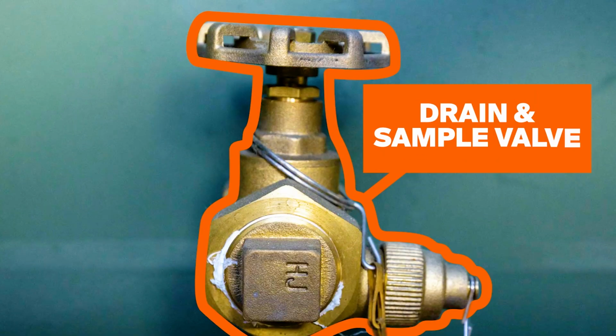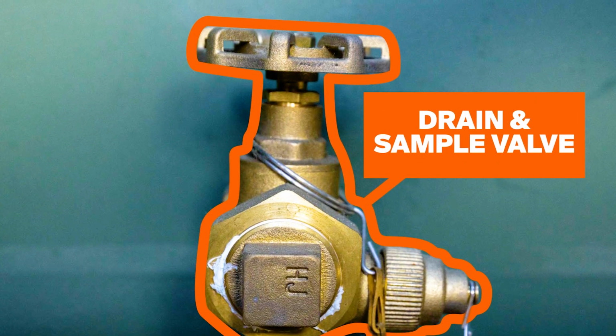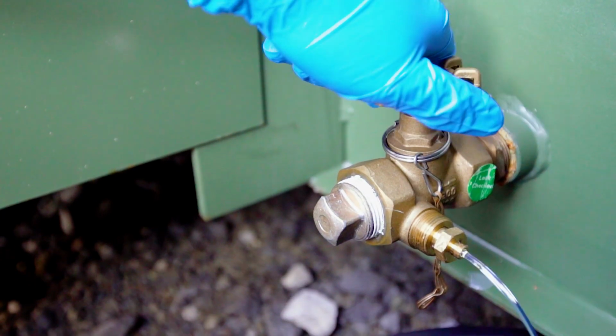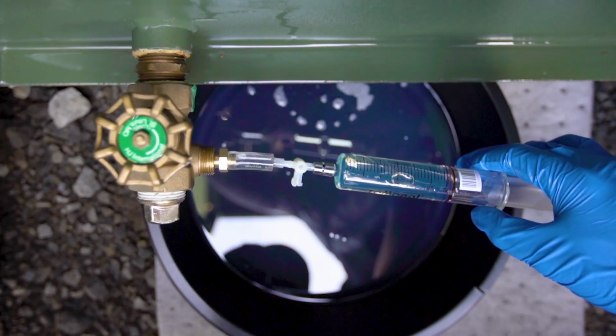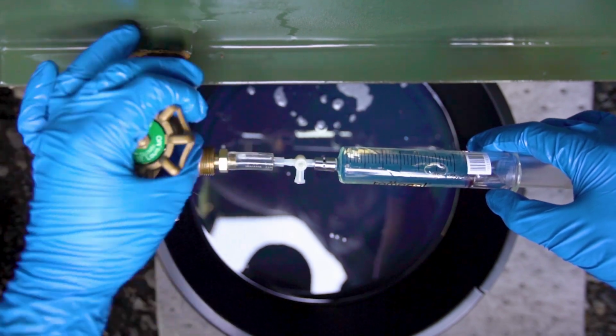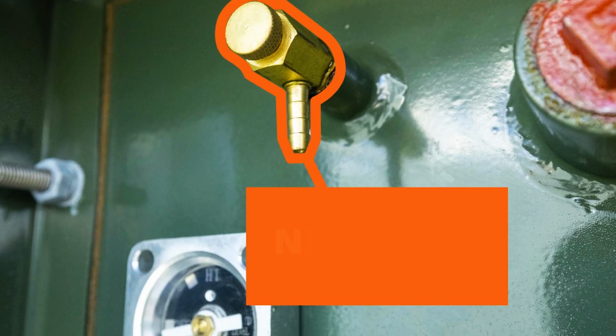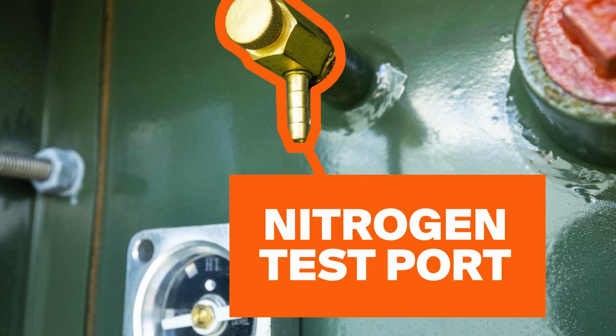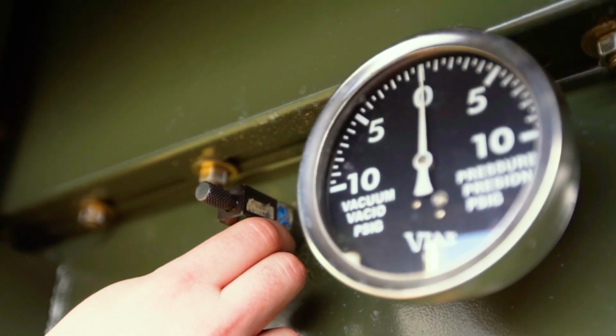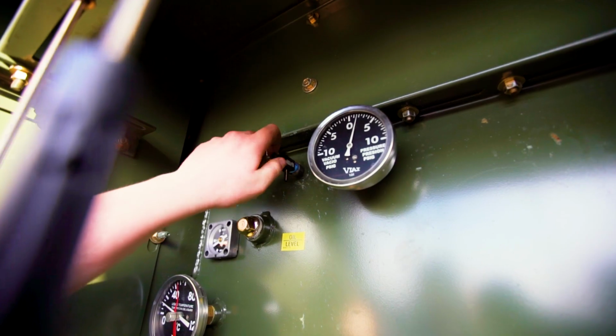The drain and sample valve allows regular test samples to be taken of a transformer's oil while the transformer's in service, such as a DGA test. The valve can also be used to drain a portion or all of the fluid inside the transformer if it becomes necessary. All liquid-filled transformers with a sealed tank have a nitrogen blanket that fills the tank's headspace. For maintenance purposes, a nitrogen test port can be added to the unit. This port can be used to recharge the nitrogen blanket inside the transformer, as well as relieve the tank's pressure.